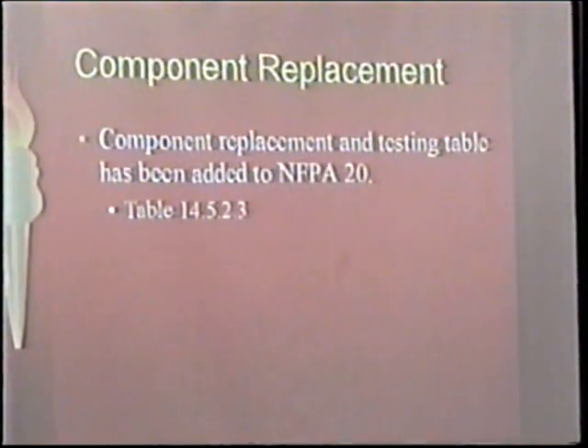They've added a component replacement testing table to 20. It's pretty interesting. It goes into the fact that when certain things get tested or changed or repaired, you may have to run a complete acceptance test to put the controller back into service. Sometimes you just have to run a churn test. Sometimes you don't have to do anything other than prove it starts. But there's a lot of items in there where a churn test or complete acceptance test is required. And they apply both to the controller and some to the pump and the motor. And those are all things we knew in good conscience we should be doing, and I always recommended it, but now they put the table in 20.